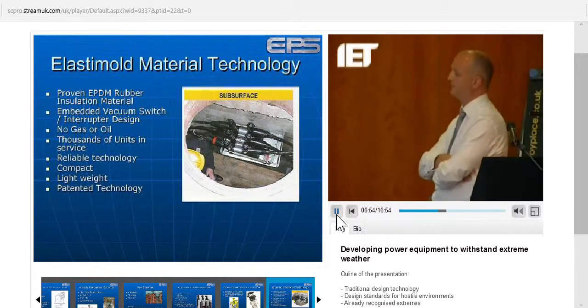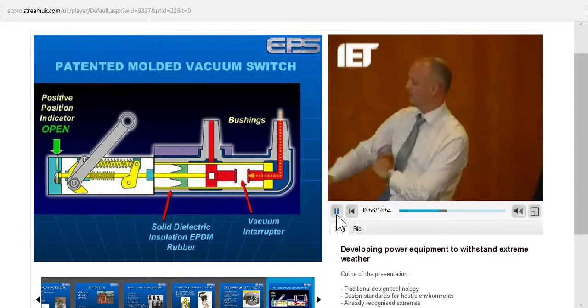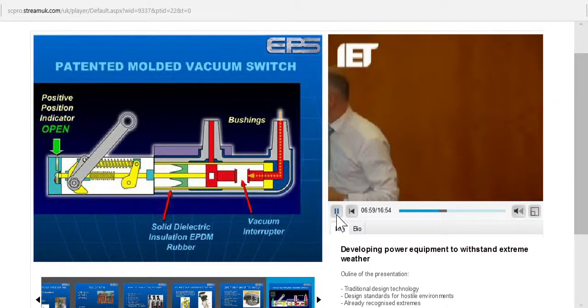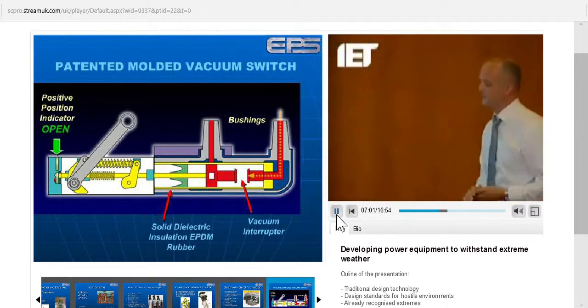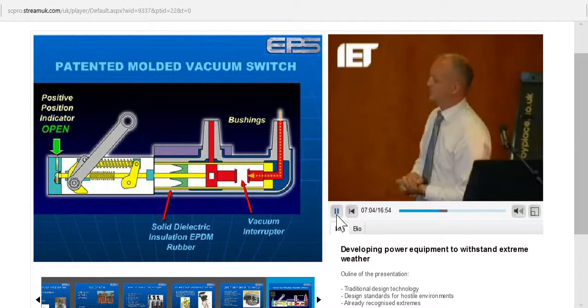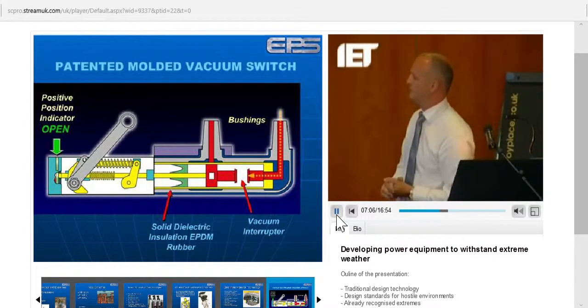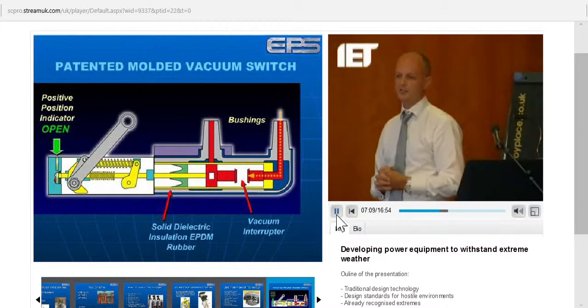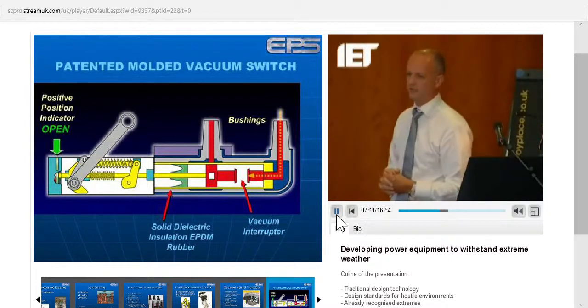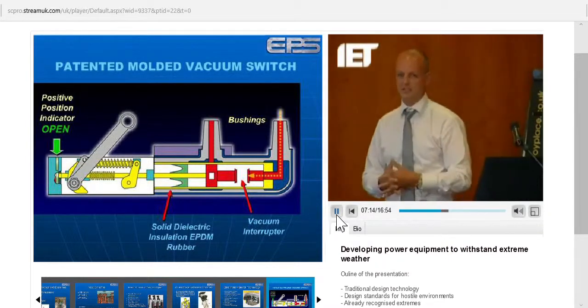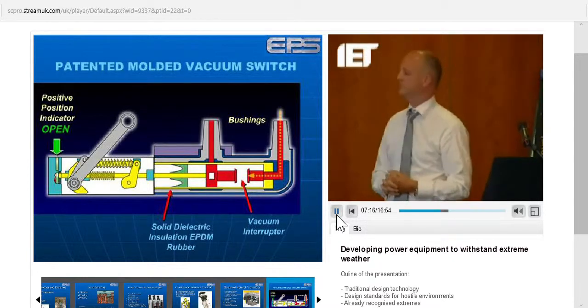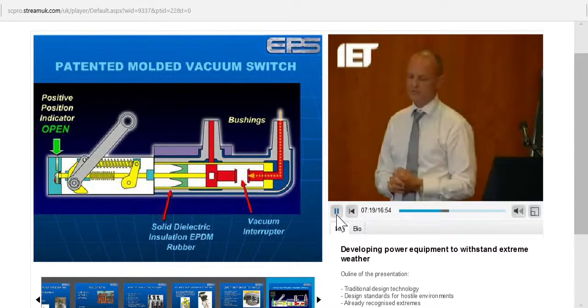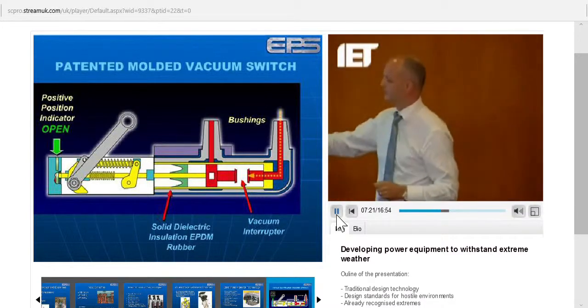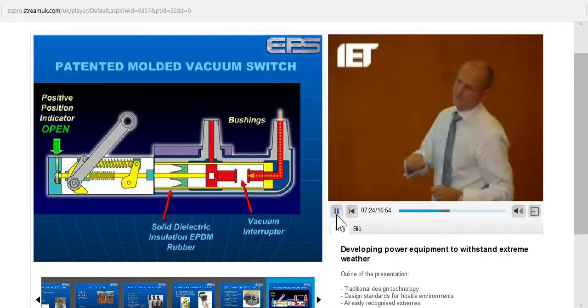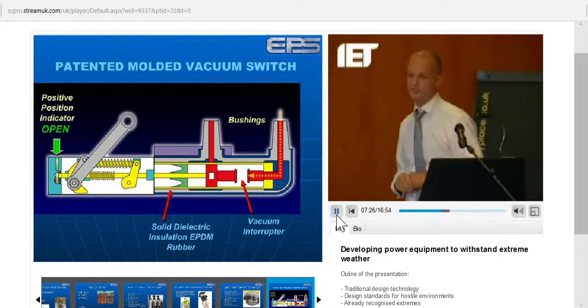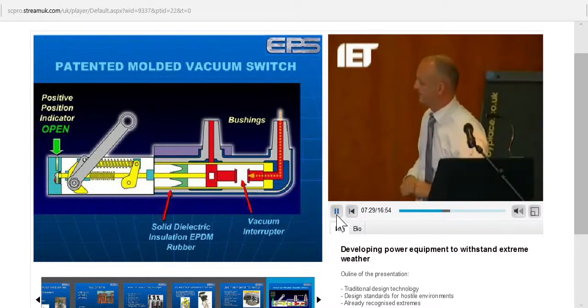The main breakthrough has been in the development of the bellow, which is shown here. Our claim is to create a truly solid dielectric circuit breaker, so we've had to get rid of any possibility of dielectric stress occurring across a gas medium or a liquid medium. In this case, the only area where there's gas is below the vacuum interrupter and between the flexible rubber bellows, which houses the drive insulator to the switch.